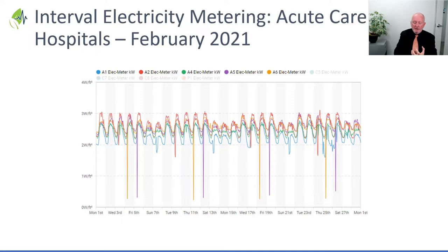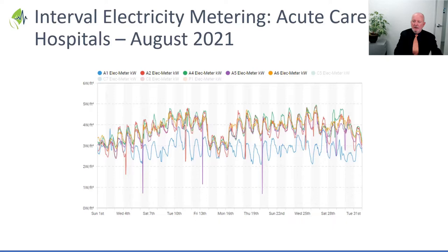So there you are in February, wintertime, no cooling plant running. Here is the equivalent in the middle of summer, August of 2021, and you see even more pronounced effects there. All of the hospitals are responding to days that are hotter and days that are cooler and milder. But you can see just how much better the performance of our blue one, A1, is in responding to cooling. It runs pretty steady through the year. And keep in mind that right through the summer, its cooling is generating all the heat it needs for reheat through its heat recovery chillers. Again, the great work that Humber River did operationally was really orchestrating that heating and cooling plant so that everything runs to the right level at the right time to maximize the overall plant efficiency.